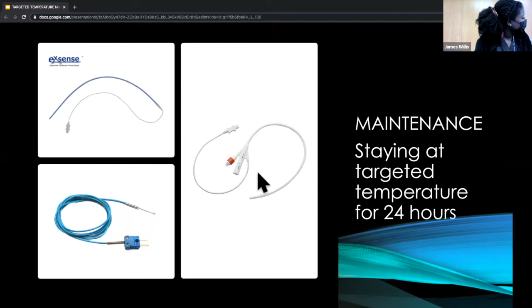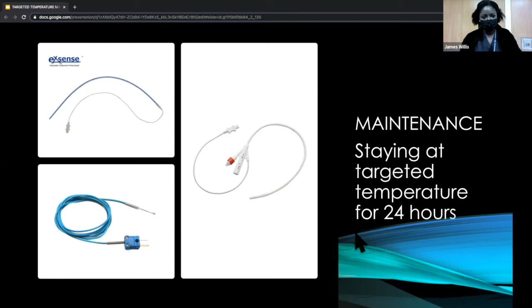There is a time lag in all of these. So the registered temperature is not going to be the same thing as what is measured, especially during the induction phase, because you're lowering the temperature quite fast. This may lead to overshooting. But what we use for the most part is going to be the esophageal thermometer. It is the most rapid and accurate reflection, and it is currently the gold standard. The average lag is about 15 minutes between what the body temperature is and what is recorded. So it's not that terrible compared to everything else.